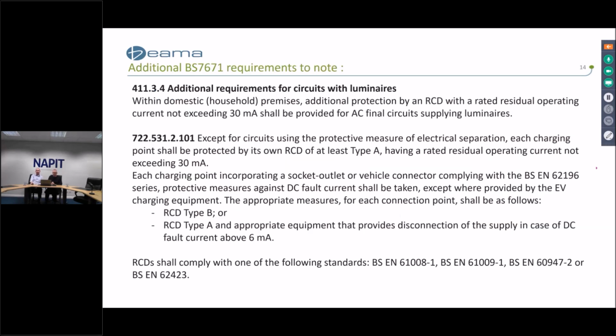A couple of additional requirements have come in with the 18th edition of BS 7671. Firstly, it should be noted that luminaires must be protected by an RCD not exceeding 30 milliamps. Frequently for residential applications, this is already covered when using a dual 30 milliamp RCD consumer unit. But it must be recognised that this is not automatically the case, and care must be taken to ensure that this regulation is complied with. So you must check to ensure for new installations, for new circuits, that any luminaires are protected by a 30 milliamp RCD.